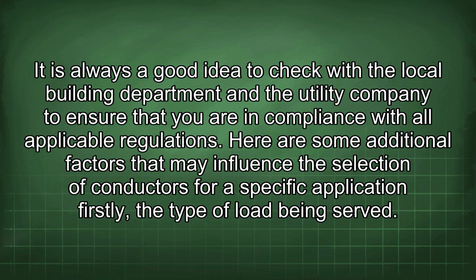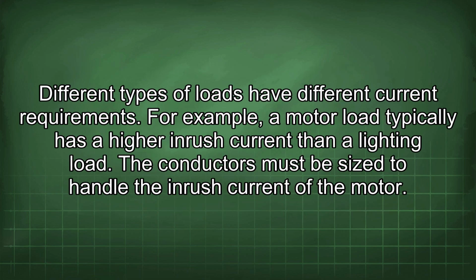It is always a good idea to check with the local building department and the utility company to ensure that you are in compliance with all applicable regulations. Here are some additional factors that may influence the selection of conductors for a specific application. Firstly, the type of load being served. Different types of loads have different current requirements. For example, a motor load typically has a higher inrush current than a lighting load.